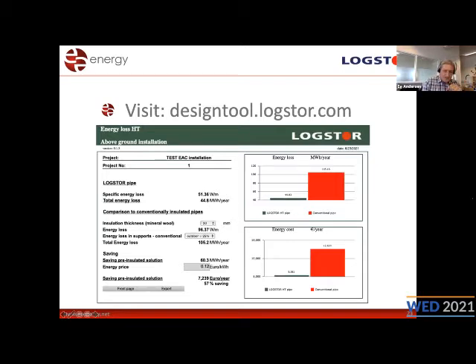So then we compare it to the existing pipe system, and that is with the normal quality we see in Northern Europe. The lowest factor we can put in is 20 millimeter. You see, the less you put in, the lower we rate the existing insulation. But just all the pictures you saw previously, they are from installations in Kenya and Uganda. And I have several pictures, several business cases where probably half of the pipes are not insulated. Condensation pipes, no insulation. So there's a lot of room for improvement in the pipe systems. But we can only put in as low as 20 millimeters.